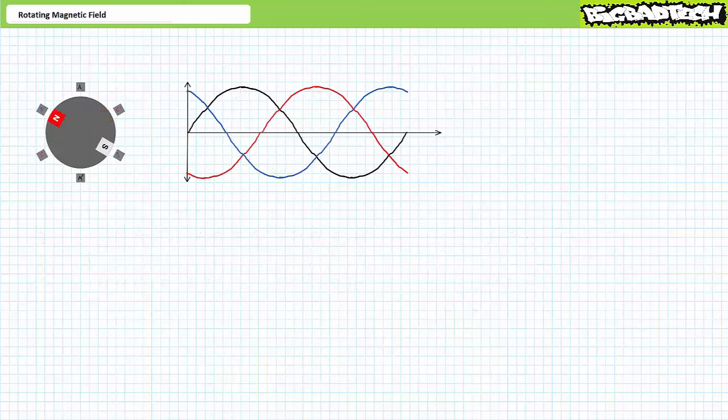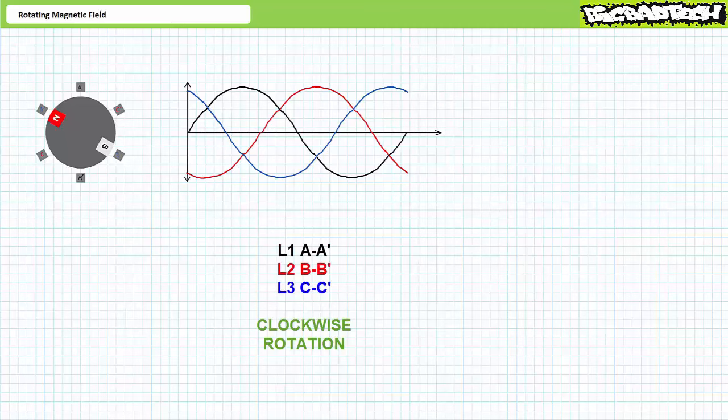Let's now examine how phase sequence determines rotational direction. With L1 connected to A, L2 to B, and L3 to C, the rotating magnetic field revolves clockwise. Three-phase AC makes it supremely easy to change rotational direction by swapping any two phases. Allow me to demonstrate.